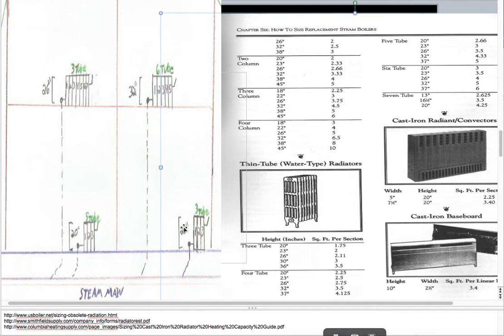Then you go around. You do that to all the radiators. So it takes a little bit of time when you're in a house, but it pays off in the end because you get a more equally sized boiler, a more properly sized boiler. Imagine you're going to create the steam that can actually fill these radiators and the steam main. You're not going to run out by the time it gets to this last radiator and you're not going to short cycle the system and blast water out of these vents either. So you go around all these radiators. You measure them. You got to get the height. You got to figure out what kind of radiator you're using.